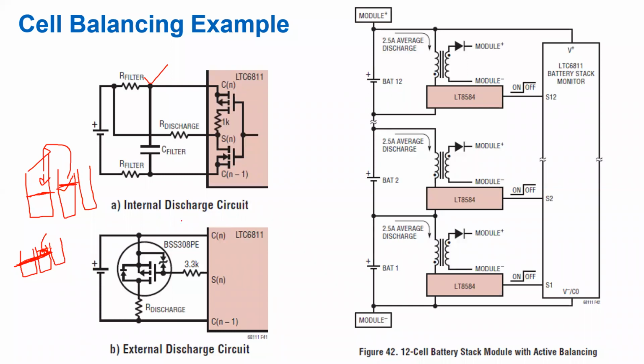That's the internal discharge circuitry and the external discharge circuitry. In the case of internal discharge circuitry, that is within your BMS front-end chipset, where you have the discharge resistance through which it is discharging. In case of external discharge circuitries, you can attach an external gate for it. For each bank or series of cells, this discharge circuit remains applicable, and its job depends on the complete voltage measurement accuracy, on how good the balancing will happen for your cell.